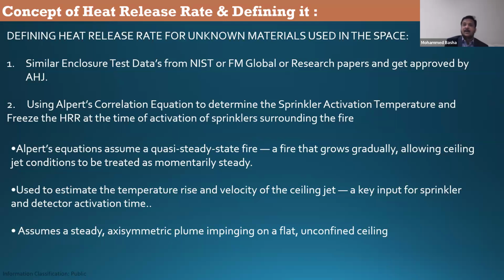You have to somehow take data or do a simulation to determine how much worst case scenario you have to take. For example, if you are designing for a stage, you have to see what is the worst stage in a real life scenario. You have to find a value for this and do the smoke management system calculations.